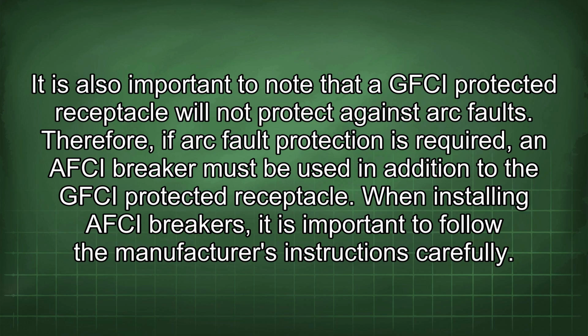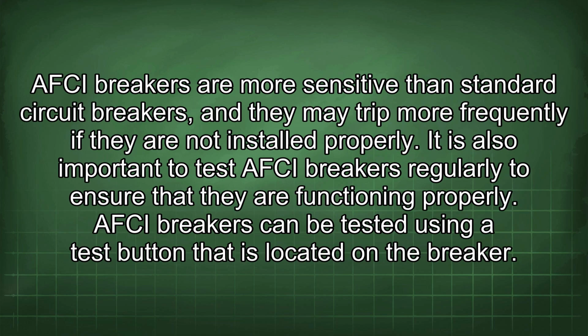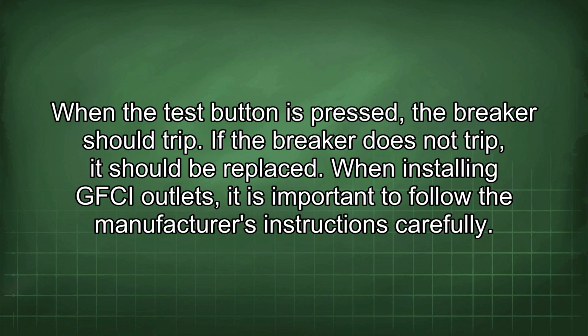When installing AFCI breakers, it is important to follow the manufacturer's instructions carefully. AFCI breakers are more sensitive than standard circuit breakers, and they may trip more frequently if they are not installed properly. It is also important to test AFCI breakers regularly to ensure that they are functioning properly. AFCI breakers can be tested using a test button that is located on the breaker. When the test button is pressed, the breaker should trip. If the breaker does not trip, it should be replaced.